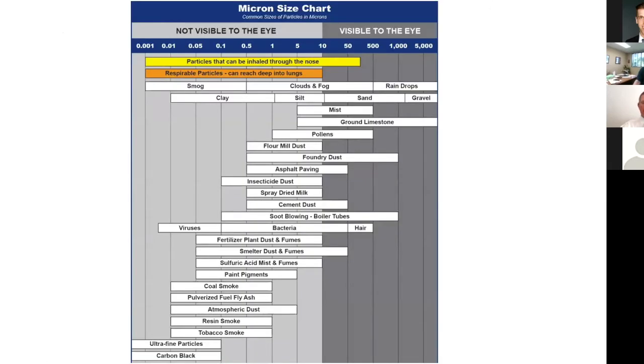Here's a chart that shows that in order to catch the virus, if I drop down on the virus, which is about right there, and I move to the right just a little bit, Bob. Right there, you'll see that the virus starts, and if I move up to the top, around 0.1 microns. And so there is where I'm trying to get to control the virus. So again, a MERV 13 will reach somewhere into that area. Now, lower grade filters can control some of the other things to my right-hand side. Next slide.